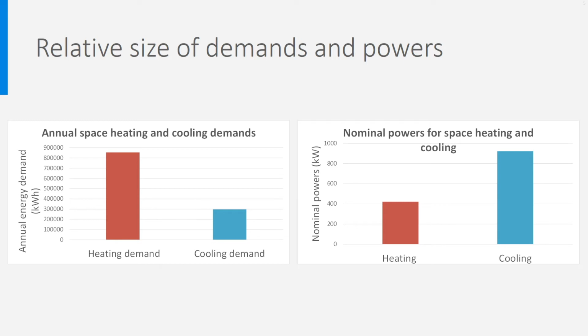The peak for heating is not high, but there is a continuous demand for heat. The peak for cooling is high, while the demand for cooling is limited to a few weeks a year. As the investment costs relate to the nominal power, cooling will need a relatively high investment, while it will not be used often. That is why taking measures to reduce this high peak is recommended. An example of such a measure is the use of external solar blinds to reduce the peak in solar gains.